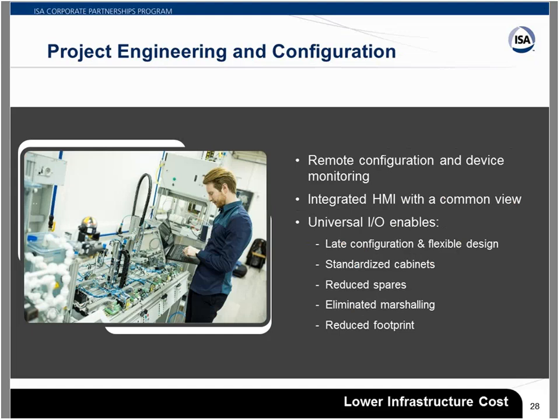An integrated system utilizing PLCs with DCS can offer remote configuration and device monitoring on an integrated HMI, providing a single view across operations. In addition, something new we've already brought to market with our DCS is starting to find its way into the PLC space: universal channel technology, universal I/O, software configurable I/O, which enables the entire cabinet to become a standard part. Some customers now build up cabinets complete with universal I/O, in small, medium, and large type footprints.